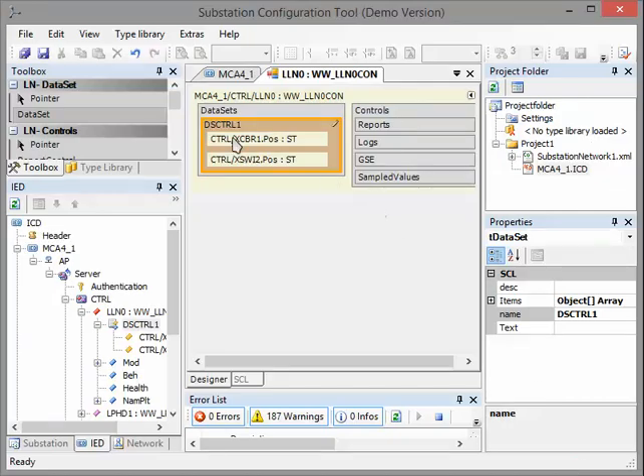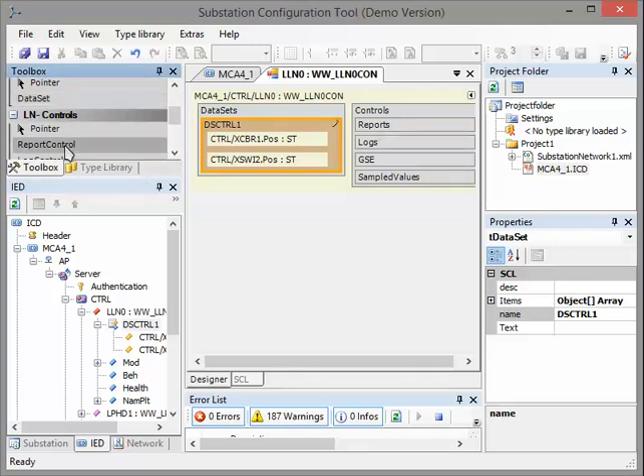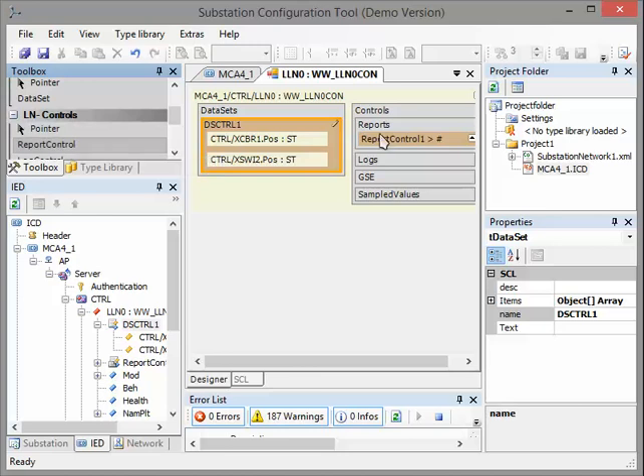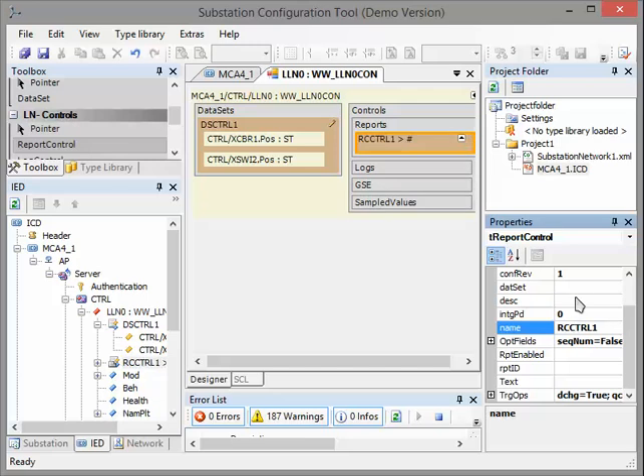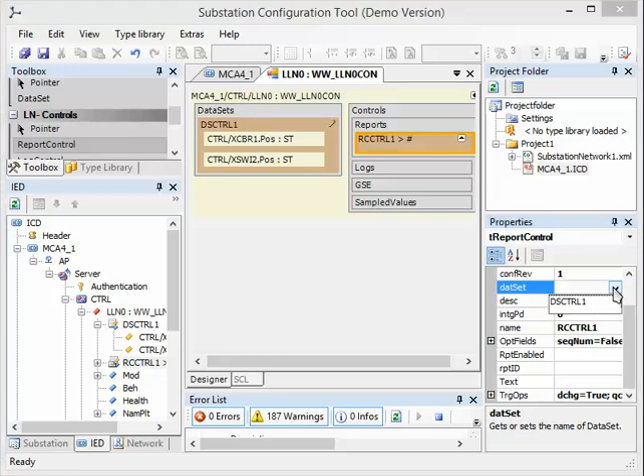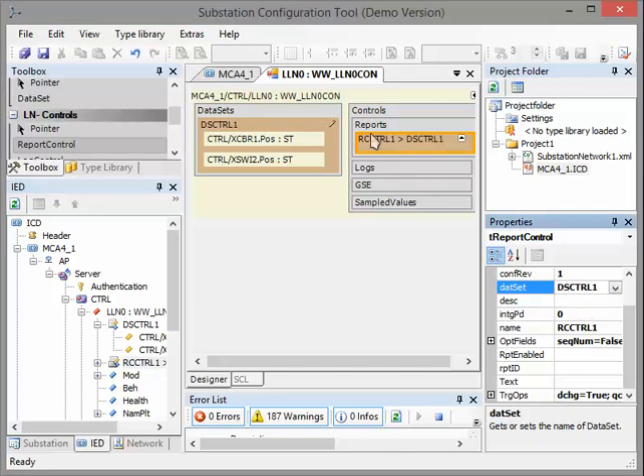Now my dataset includes all information about the position of my circuit breaker and my switch. The next step is to insert the report control block. We click here to add the report control block. You will see it was added. We click on it to change some properties. The first thing we change is the name — 'Report control 1' is not very clear, so for example we choose 'reportControlCTRL1'. The next step is we choose the dataset. We remember we created 'datasetCTRL1'. Now we choose it — this links the dataset to the report control block.